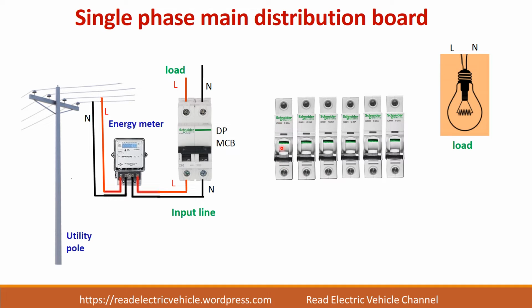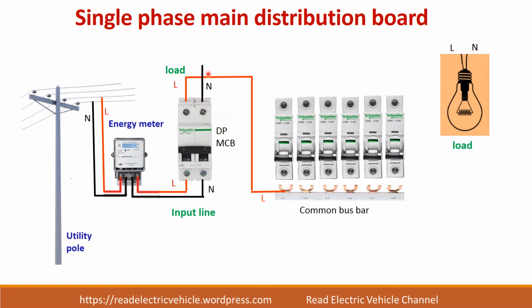Now this switch needs input which is a phase line. So we can use a common bus bar, and you have to give all these switches a phase line. So let us connect it. From here connect the line wire here. Then through a common bus bar all the switches can be connected. This helps to reduce the manual connection here. Next, to the other terminal of the MCB we have to connect the loads, or the line of the load is connected from the other end. So we can see here the line wire is connected to the load through a switch. So whenever any fault occurs, this will trip.